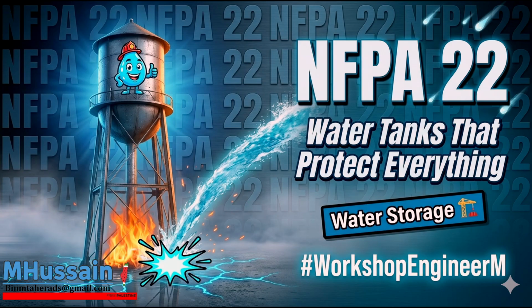Beyond the state change of water into ice, engineers must account for the mechanical stress caused by these wild temperature swings. As the ambient temperature shifts from a freezing winter night to a blistering summer afternoon, the metal itself expands and contracts. Figure B1 in the annex details a critical mechanical solution for this: the use of 4 elbow swing joints on the piping connections.